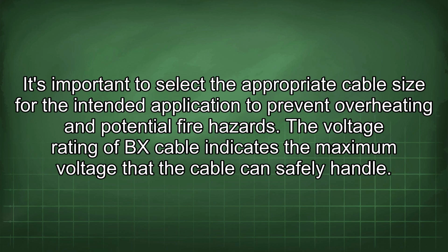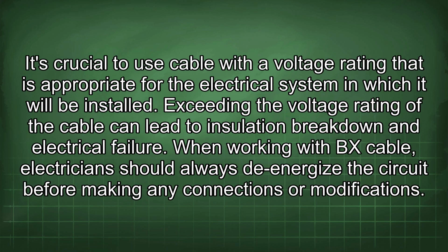The voltage rating of BX cable indicates the maximum voltage that the cable can safely handle. It's crucial to use cable with a voltage rating that is appropriate for the electrical system in which it will be installed. Exceeding the voltage rating of the cable can lead to insulation breakdown and electrical failure.